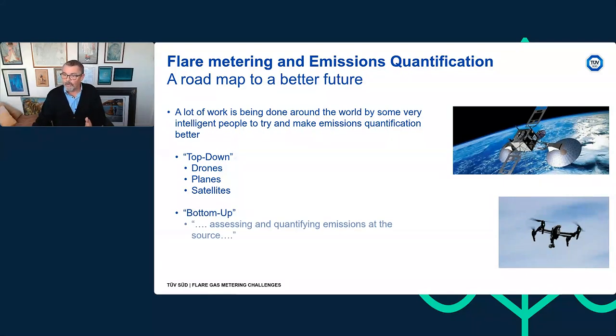There's the bottom-up approach, which is assessing and quantifying emissions at source, and this is the part that I'm involved with, trying to make flare metering better and make emissions quantification better. As a matter of interest, OGMP 2.0 regards the gold standard as being able to reconcile top-down and bottom-up measurement, as a way of verifying on an ongoing basis that your emissions quantification is correct, and by default that means your flare metering is correct.